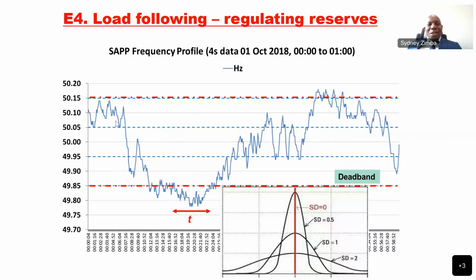We do monitor how the power frequency is controlled by our control area operators. It may be like this, sharp. If we control it exactly at 50, it will be a straight line here. It's not easy. It's like you want to drive from work home only at 50 kilometers per hour. In all those curves, all those traffic lights, it's not easy. The same with our power frequency. You can't control it exactly at 50. You then strain your controllers at the power stations, those governors, the mechanical systems, the wear and tear will be increased. Hence, we brought in this dead band. At the same time, we don't want to have this flat curve with a standard deviation of 2. It means you are always outside the dead band.